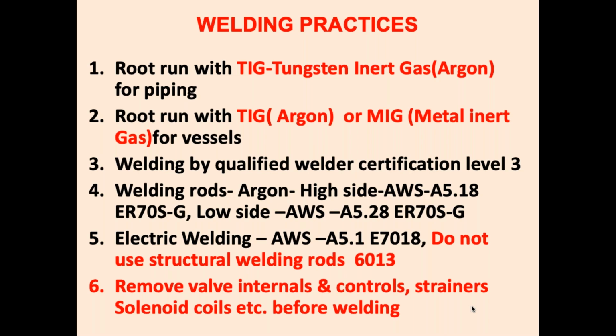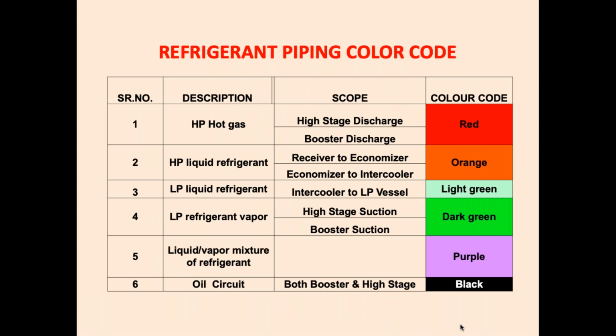Otherwise, welding is a very high temperature process and your internals, strainers, and coils will get damaged. So this is an important issue. The next slide, piping color code, very important. HP gas, hot gas pipe, booster gas, receiver to economizer, what colors to be provided. Economizer, I have given the colors.